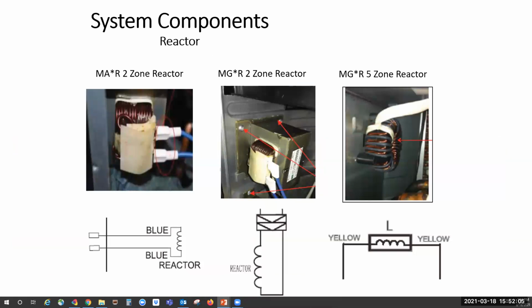Now the reactor. Checking your reactor, turn off power, unhook the wires. This is just several pictures of different kinds of reactors. Basically, it looks like a big transformer, but you're looking for 1 ohm or under. If you have anything over 1 ohm or the reactor is opened or grounded, you need to replace it. So just remember, if it's over 1 ohm, you're going to have to replace it.